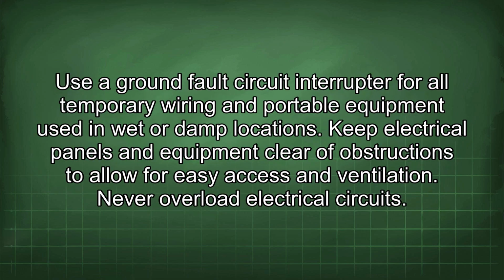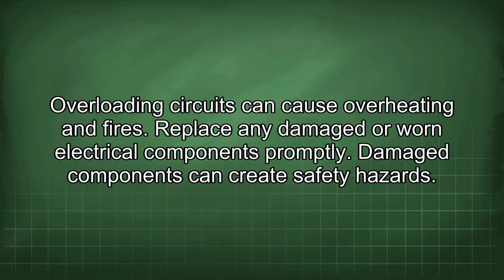Use a ground fault circuit interrupter for all temporary wiring and portable equipment used in wet or damp locations. Keep electrical panels and equipment clear of obstructions to allow for easy access and ventilation. Never overload electrical circuits. Overloading circuits can cause overheating and fires. Replace any damaged or worn electrical components promptly. Damaged components can create safety hazards.